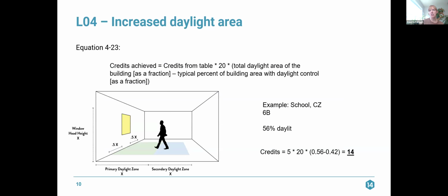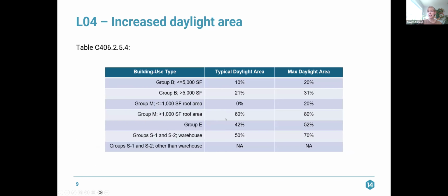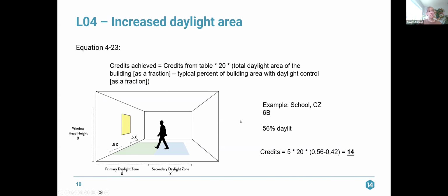Equation 4-23, the credits achieved are going to be the base credits from the table times 20 times the total daylight area of the building as a fraction minus the typical percentage of the building area with daylight control as a fraction. So we're going to use a school as an example in climate zone 6B. We're going to say that it's 56% daylit, so there's a lot of solar tubes and skylights. The credits under equation 4-23 would be 5 times 20 times 0.56 minus 0.42, right? We go back to this group E, the typical daylight area, and that gives us 14 credits.